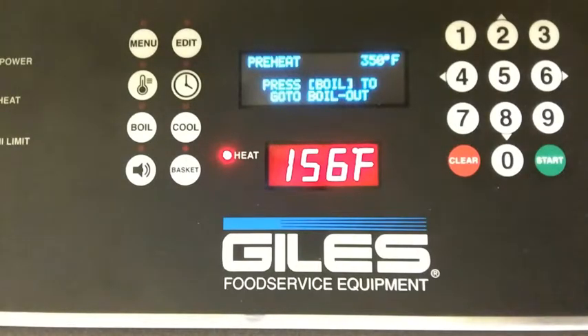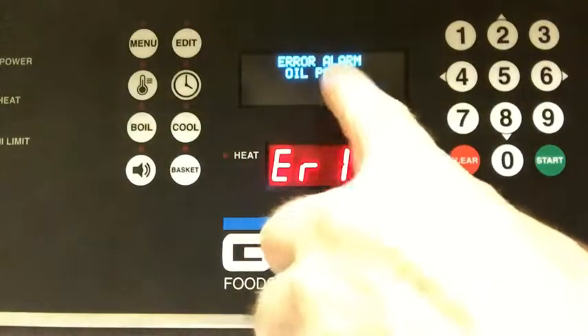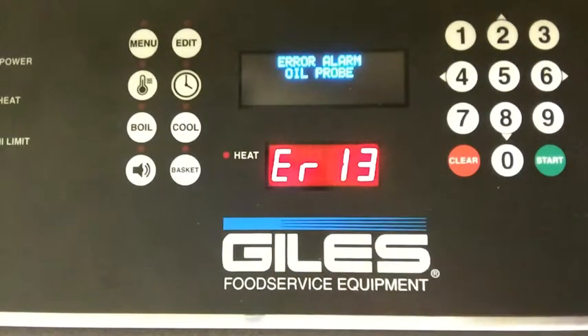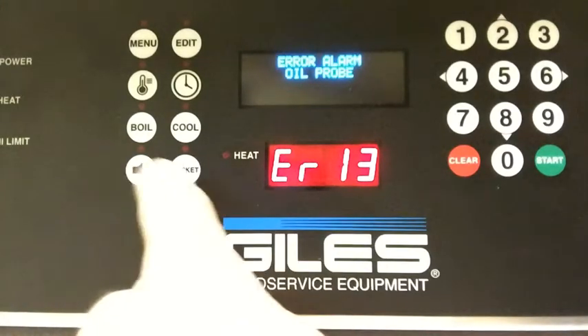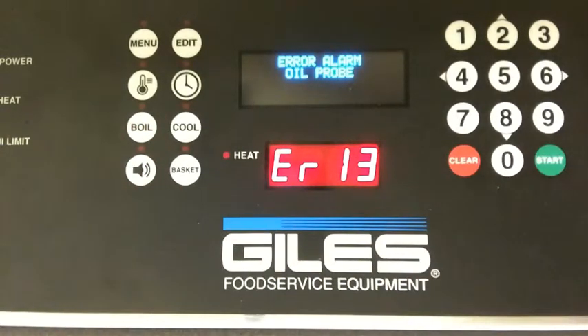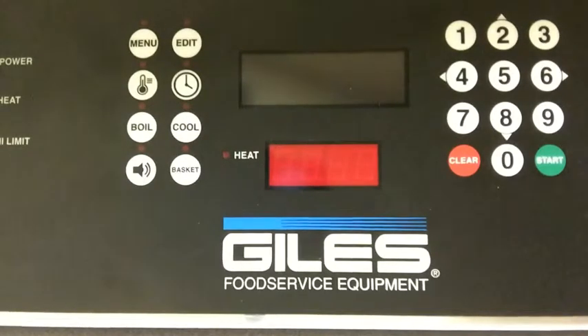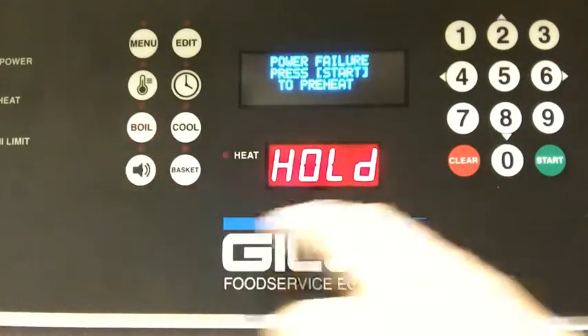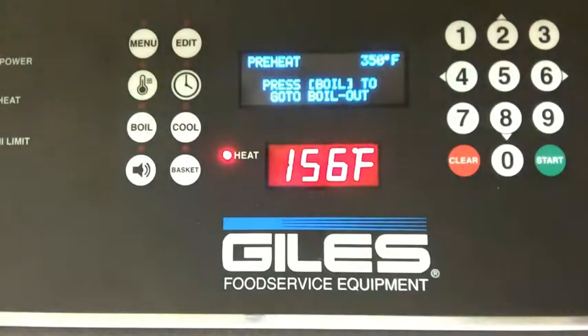Some of the common errors that might come up if they were to have some issues: if indeed you somehow lose your variable probe, which is your oil temperature probe, you will get an error that will come up and tell you that there's actually an error. And here it is, the error alarm oil probe, an ER13 error. Now the only way to clear that error is to clear the problem. You cannot press the clear, it won't go away, it'll just go into alarm. But once you have it fixed, you have to power down and power back up. Of course it'll run through its diagnostics. It's going to give you the power failure, press start, and now you've got that back.